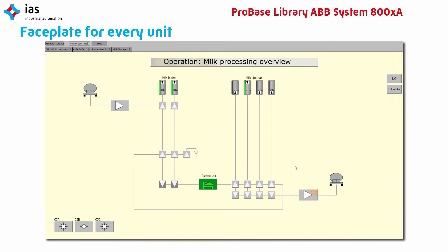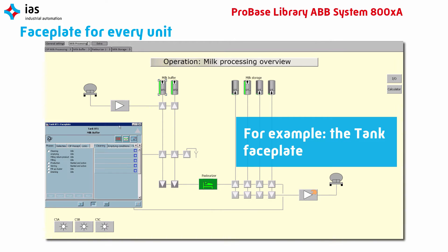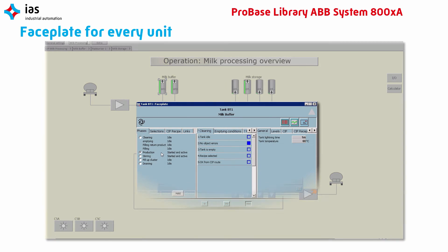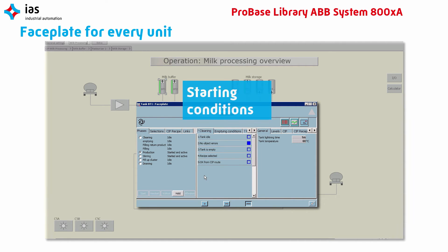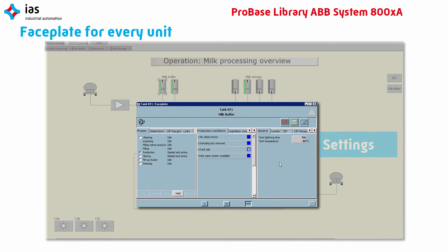Every unit has its own faceplate. Let's have a look at one of these faceplates — for example, the tank faceplate. On the left, you can see the functions of the tank, like cleaning, emptying and production. In the middle, you can see the starting conditions of every function. These conditions give the operator a clear overview of process and program interlocks. On the right, you can see the settings of this tank, like the tank temperature and the tank high and low level settings.